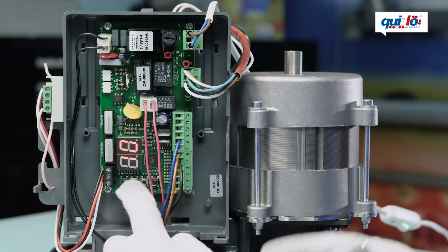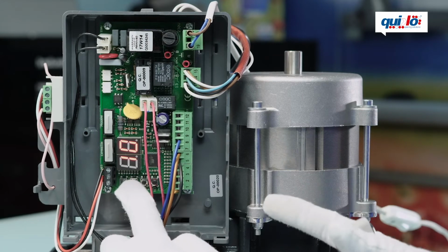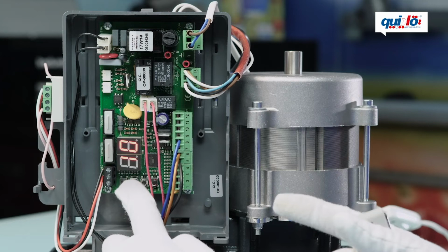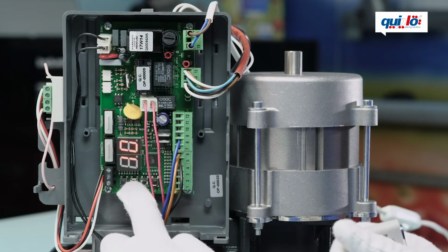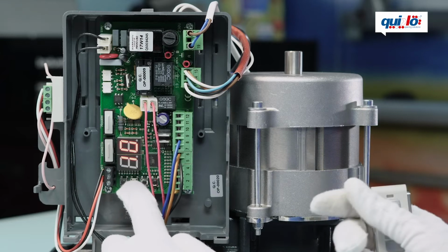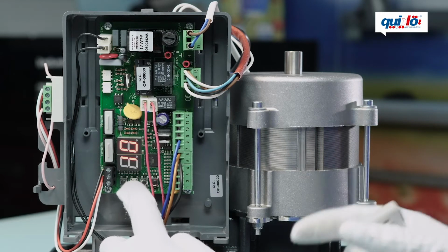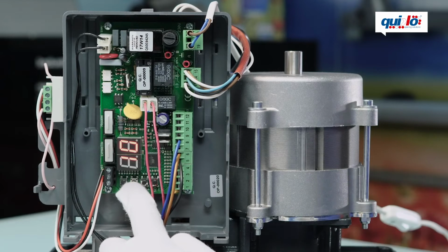It's not important if it reaches the limit switch earlier than the 10 seconds. That's why we recommend to leave slow down for at least 10 seconds. What is important is that there is enough time during slowdown to reach the limit switch.